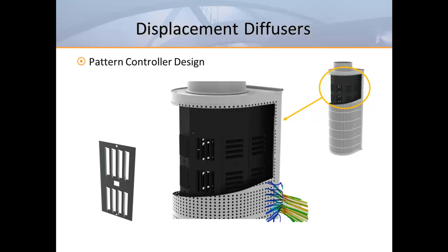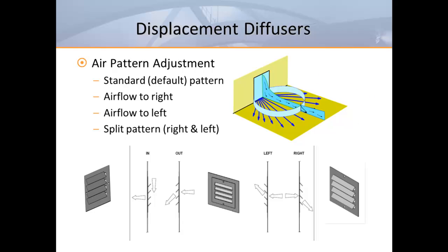At this point you may begin to wonder why adjustable diffusers are recommended at all. The answer is easy — adjustable diffusers are recommended because of the adjacent zone. It's important to provide some means of fine tuning the air pattern. As anyone in the construction industry knows, things don't always work out perfectly and sometimes spaces change purpose. For these reasons, adjustable diffusers are recommended to accommodate changes in room layout or seating locations.